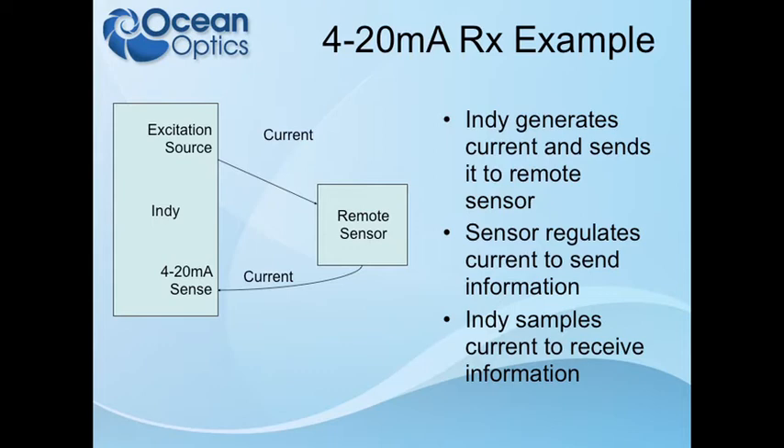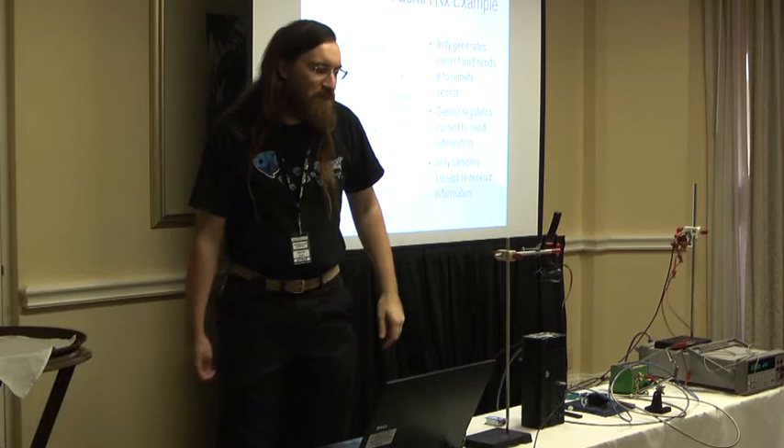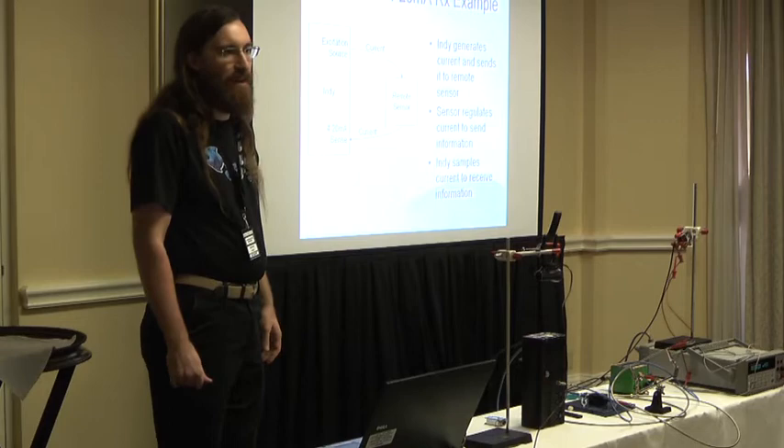To receive, a typical setup would have an excitation source within the Indy set to 10 or 20 volts — though if you're using the 4 to 20 transmitter in the Jaz, you want 20 volts since 10 is not enough. Current flows out to a remote sensor — a pressure sensor, temperature, pH, O2, or position indicator — which regulates the current, and the returning current is sensed in the Indy, providing a path back to ground. You can use the Indy as a transmitter or receiver, and it can technically be both, though that's really useful only for diagnostics. The Indy also provides eight general-purpose digital inputs and outputs.